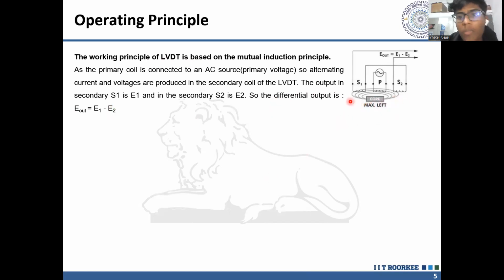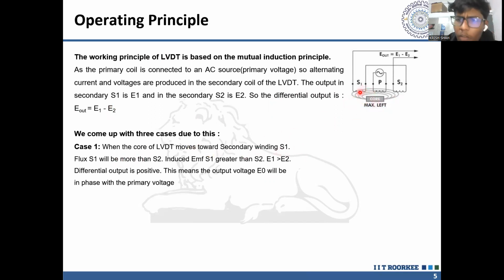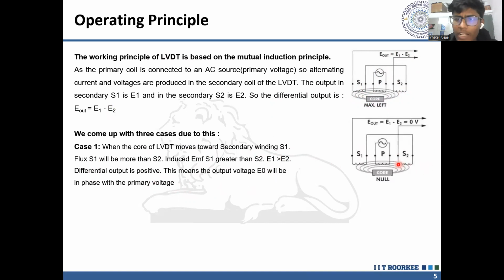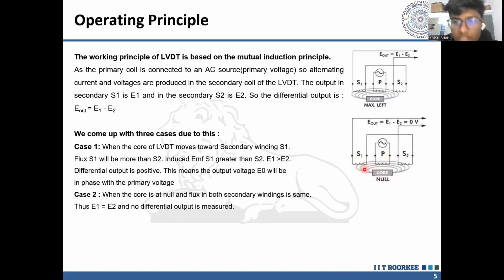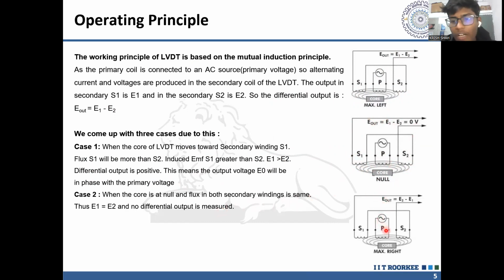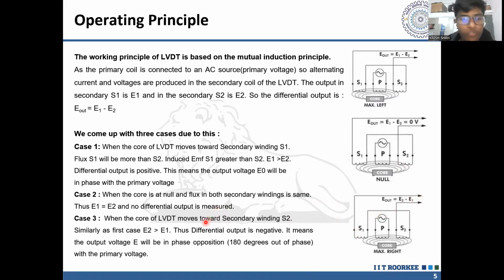When the core is at the maximum left of its position, moving towards the S1 side, the flux in S1 would be more than the flux in S2, and therefore the EMF in S1 would be greater than the EMF in S2. Thus we have an output voltage E out which is positive and in phase with the primary voltage. In the second case, the core is at the null position at the center. Here the flux in S1 and the flux in S2 are equal, and thus we get no output, zero voltage. When the core moves to its rightmost side towards the S2 side, the flux in S2 is greater than the flux in S1, so the EMF in S2 would be greater than the EMF in S1. Therefore, we have a voltage that is opposite in phase to the primary voltage applied to the primary coil.